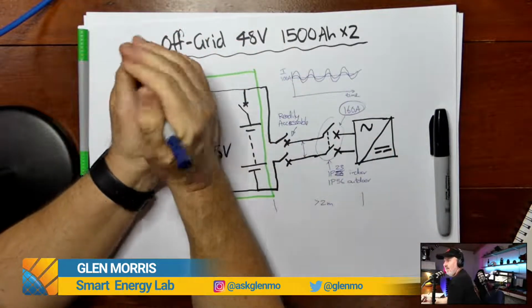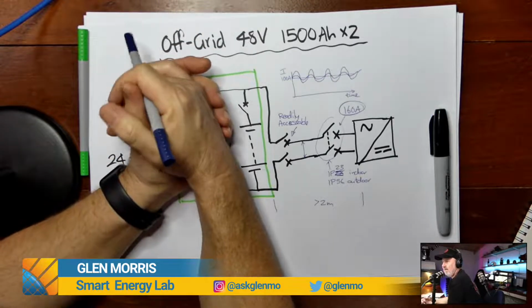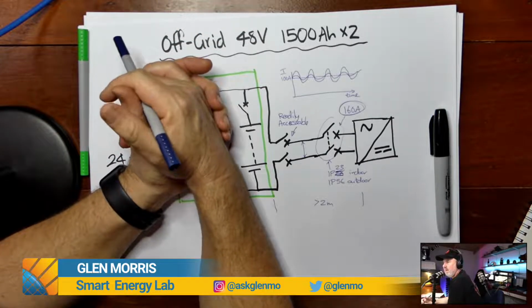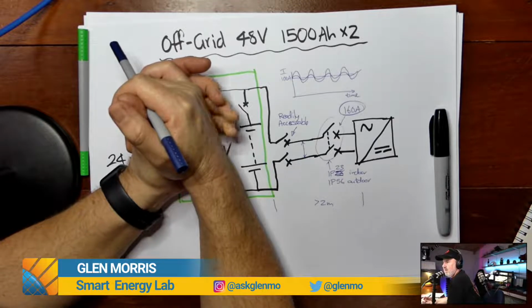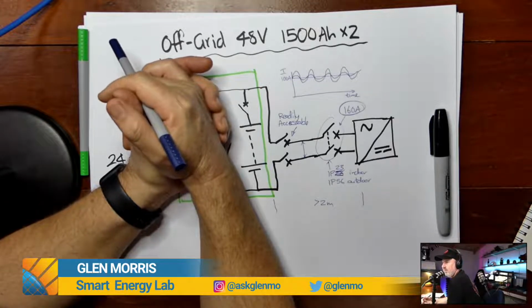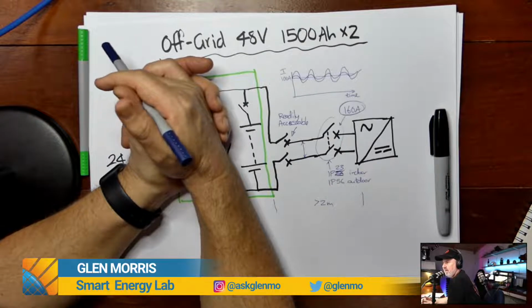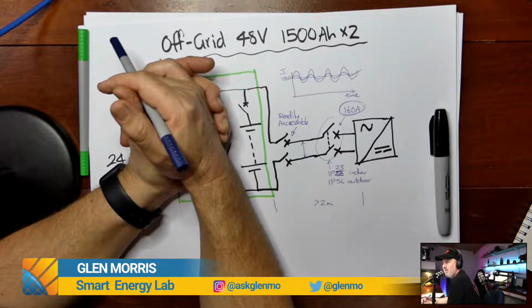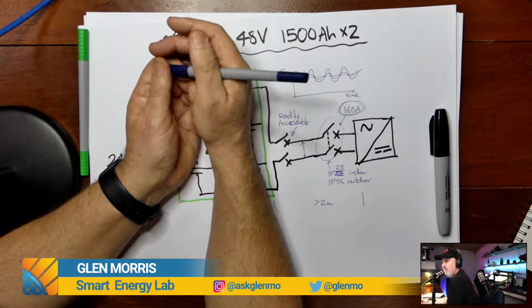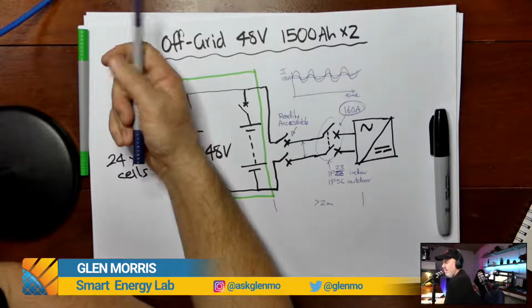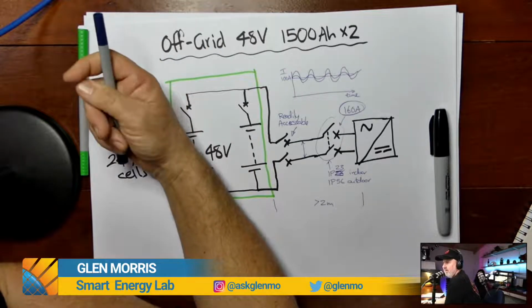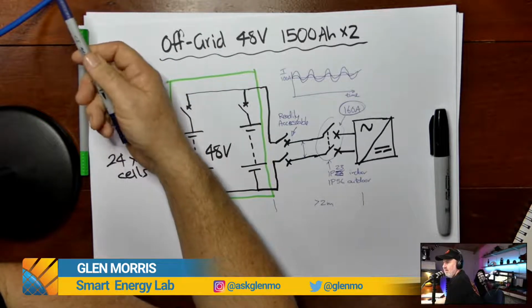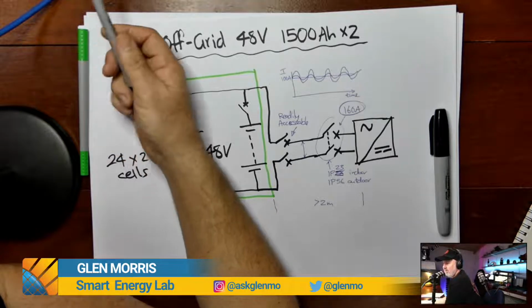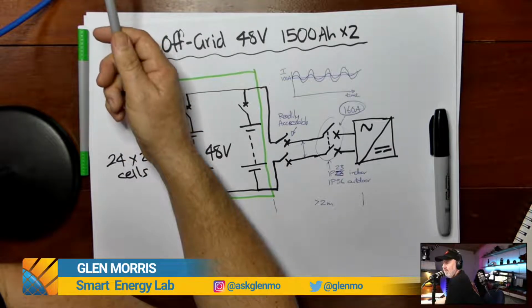Okay, so all right, we've got a question here from Anne. Thanks, Anne. So the question is, hey Glenn, is the circuit breaker in the LG Chem HV 10 kilowatt hour battery considered readily accessible and therefore sufficient for the main battery isolator? You just undo a latch to get at it. Well, I don't require a tool. It might be a little bit fiddly, like you've got to lift a little safety clip with your finger and open it, and then there is a conventional no-arc circuit breaker behind that cover, and that can be operated.